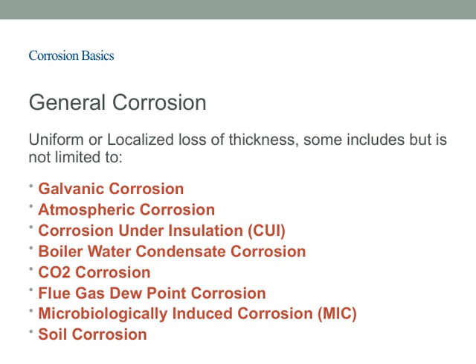Boiler water condensate corrosion happens when condensate forms inside boilers, leading to corrosion of internal surfaces. CO2 corrosion is particularly relevant in pipelines and systems where carbon dioxide dissolves in water, creating acidic conditions that accelerate rust. Flue gas dew point corrosion occurs when flue gases cool and condense, leading to corrosive attacks on boiler or chimney components. Microbiologically induced corrosion, or MIC, involves bacteria that produce corrosive byproducts, significantly impacting pipelines and tanks. And finally, soil corrosion refers to the deterioration of buried structures due to contact with soil, moisture, and microorganisms.